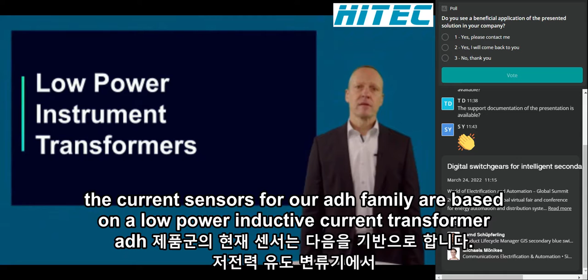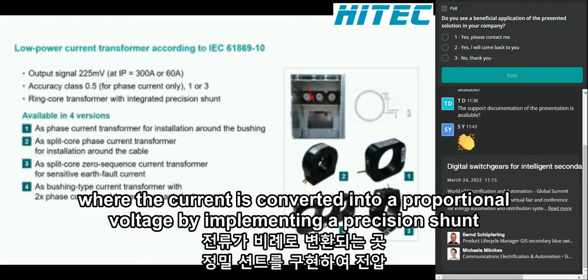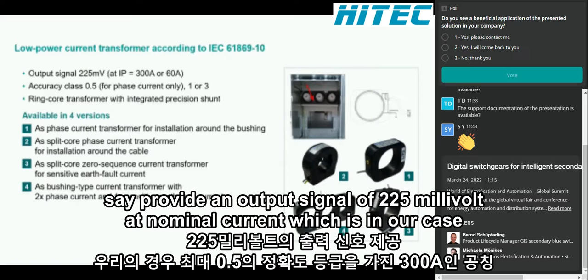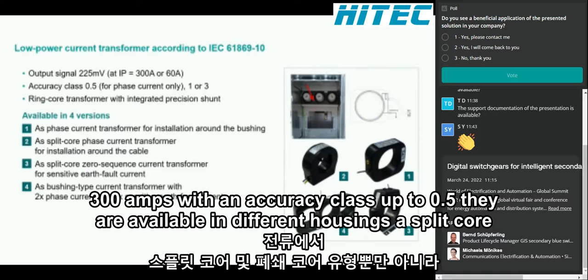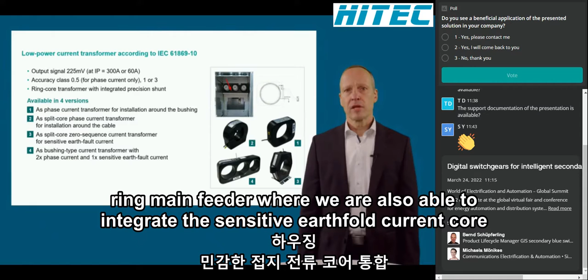The current sensors for our 8DJH family are based on a low power inductive current transformer where the current is converted into a proportional voltage by implementing a precision shunt. They provide an output signal of 225 millivolt at nominal current, which is in our case 300 amps, with an accuracy class up to 0.5. They are available in different housings as split core and closed core types, as well as a combined housing, especially for the 8DJH ring main feeder, where we are also able to integrate the sensitive earth fault current core.